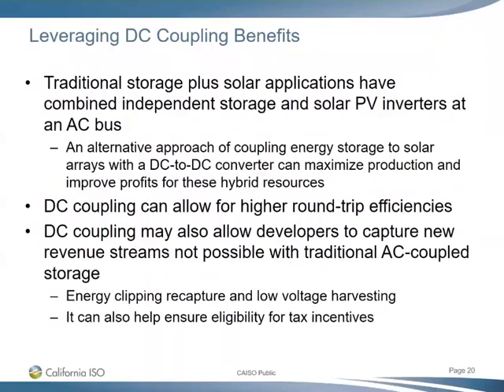Leveraging DC coupling benefits is the final driver identified. Some developers have noted that DC coupling can lower overall capital costs and allow for higher round trip efficiency. Other benefits include energy clipping recapture, low voltage harvesting, and ensuring capture of the investment tax credit. However, Chris noted hearing discussion that DC coupling sizing may be limited to perhaps smaller projects, possibly below 30 or 40 megawatts, so the cost-benefit needs to be done by individual developers. The ISO expects that some projects will pursue this approach.